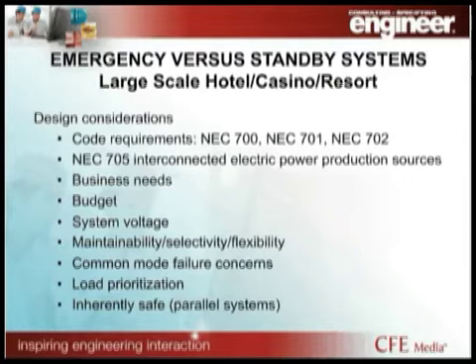One other issue is that when you design the systems and you specify them, they need to be inherently safe. If an operator goes up to a board and tries to close in two sources that are out of sync, depending on how far out of sync they are, that could be a line-to-line fault, which in electrical terms is bad. So you really have to make sure that they're not able to do something that's unsafe, and that's usually done with interlocks, with sync check. I mean, there are all different ways that you can make sure that the gear is inherently safe. And ASCO, Russ Electric, your more prolific vendors out there are pretty familiar with the hardwire technology that needs to go behind the programming to keep the operator safe.